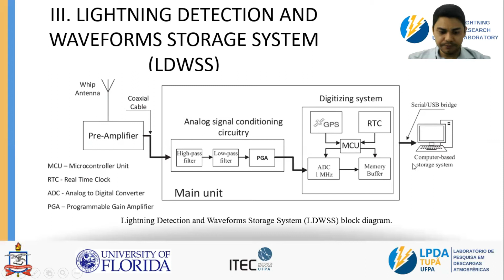So here's the main board, the main unit, that consists of an analog signal conditioning circuitry and a digitizing system. The analog conditioning circuit includes a 500 kilohertz low-pass anti-aliasing filter here, a 30 Hz high-pass filter here, and a programmable gain amplifier here. The sample rate of the digitizing system is up to 1 megahertz. The digitizing system has an RTC, real-time clock, which is synchronized with a GPS module here. The digitized waveforms and the respective timestamps are sent to a computer-based storage system via a serial USB bridge here, and the waveforms are stored in the PC.